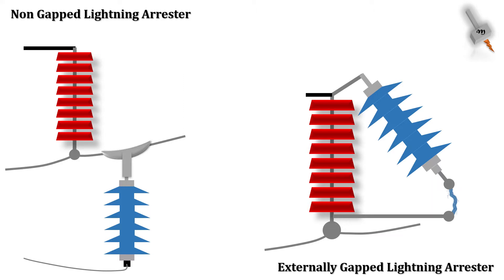Both designs are different versions of Line Surge Arrester which are used for transmission line protection. In NGLA, the arrester unit is connected electrically in parallel to a string insulator or composite insulator in a transmission line. In an EGLA, the arrester unit is placed in parallel to the insulator but they are not electrically connected from phase to earth. Rather, there is a spark gap in series with the Lightning Arrester.